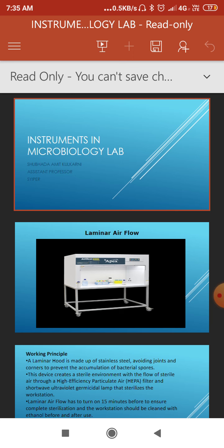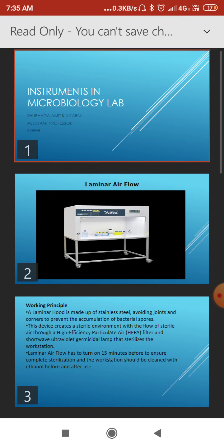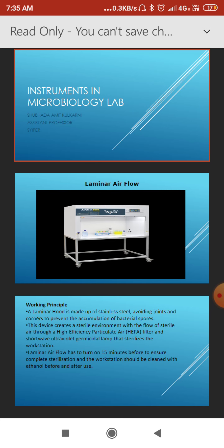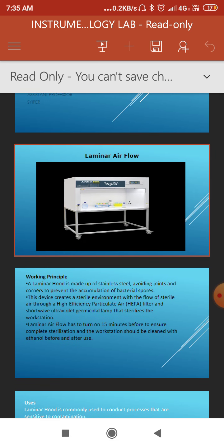What is laminar airflow? Laminar airflow is also called unidirectional airflow — it means straight and uninterrupted airflow. Laminar airflow cabinets are generally used where protection is required for the work and product only. We use laminar airflow because we require an area which is free from microorganisms.